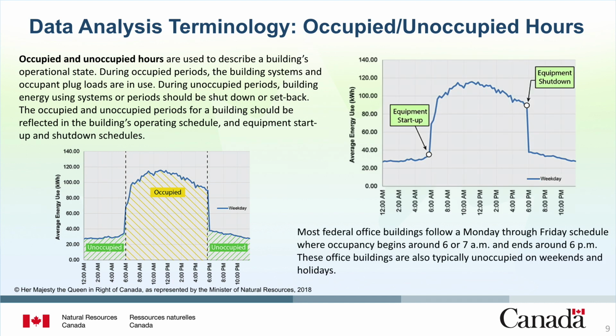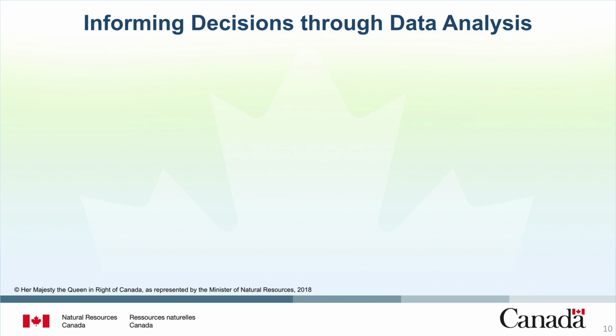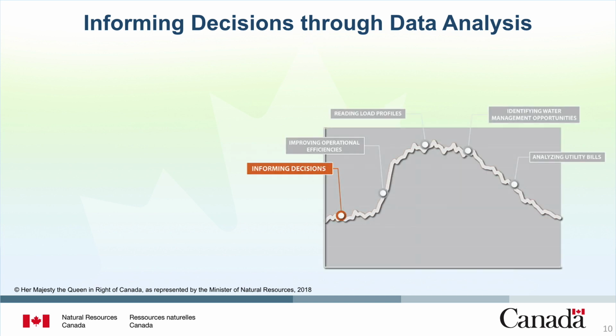Most federal office buildings follow a Monday through Friday schedule where occupancy begins around 6 or 7 a.m. and ends around 6 p.m. These office buildings are also typically unoccupied on weekends and holidays. The load profile in the graphs illustrates that energy usage spikes around 6 a.m. and declines sharply around 6 p.m. Therefore, the occupied period is between 6 a.m. and 6 p.m., and the unoccupied hours are from 6 p.m. to 6 a.m. Now let's briefly discuss how to use data analysis to inform decision-making.